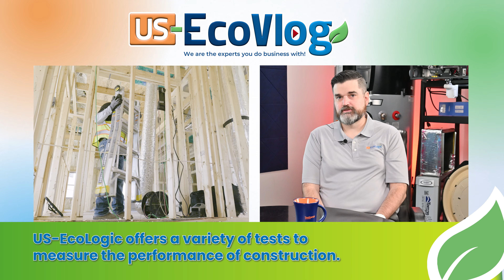The other option we offer is HVAC grading. That takes the duct testing even further, and the load calculation check further. With the duct blasting, we'll also do an airflow test, making sure not only that the duct system is sealed, but that the air handler has been set to the right speed so the correct CFM is going through the duct system.